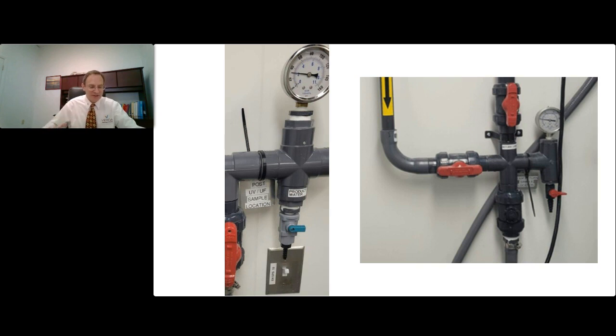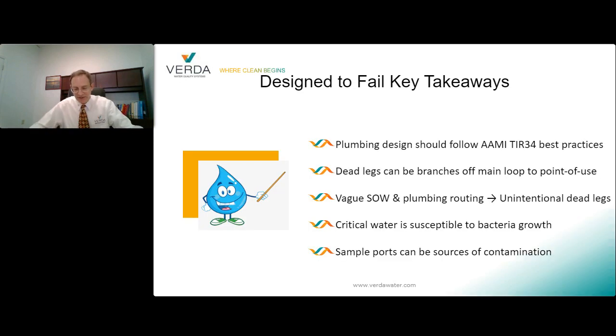The AAMI protocol is for, at a minimum, monthly disinfections. And the rationale, I believe, in the hospital was, well, this new SPS has not gone live, so it isn't necessary to regularly disinfect the system. So, key takeaways. One, the devil's in the details. The best intention of the management or the general contractor is lost if the plumber doing the work doesn't understand the importance of maintaining minimal lengths on dead legs.